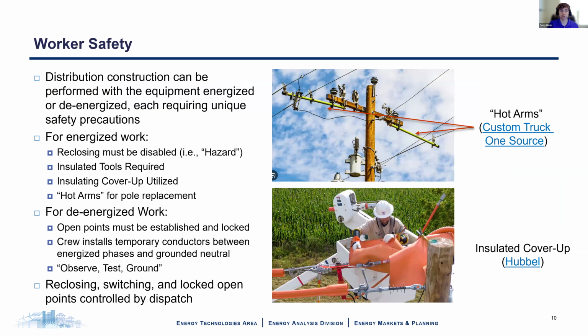Operations is also responsible for worker safety, which is one of the most important aspects of dispatch and an operations supervisor's job. Construction can be performed with equipment still energized. It can be de-energized, but it doesn't have to be. And there are unique precautions that you have to take for energized or de-energized work. So if you're doing construction with the system still hot, obviously you need to take precautions. So the first is that reclosing has to be disabled.